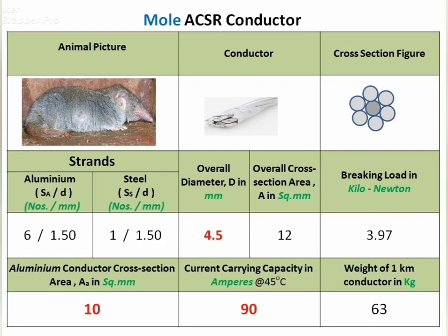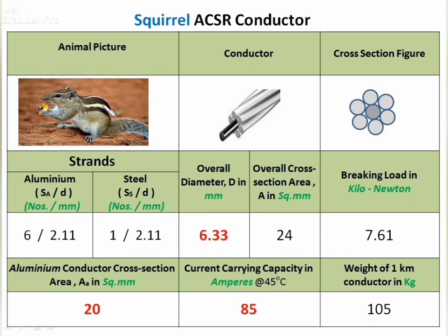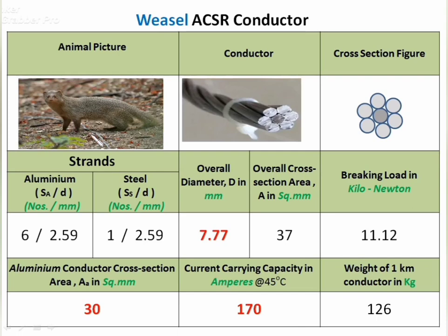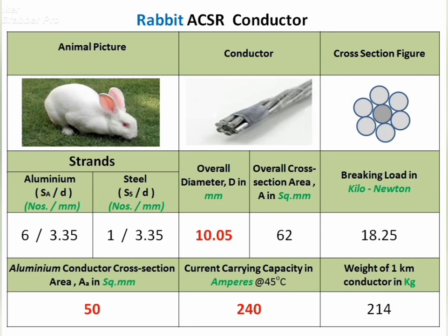Now we will see various types of ACSR conductors. Mole ACSR has six aluminium strands and one steel strand; overall diameter is 4.5 mm, cross-sectional area 12 mm², aluminium area 10 mm², current capacity 90 A, and weight 63 kg/km. Squirrel has area 20 mm² and 85 A current capacity. Weasel and Mongoose type has 30 mm² area and 170 A capacity. Rabbit has 50 mm² area and 240 A current capacity.